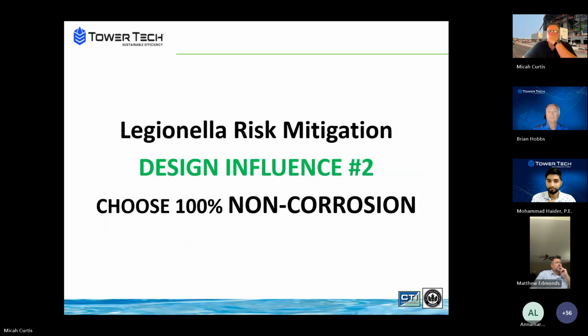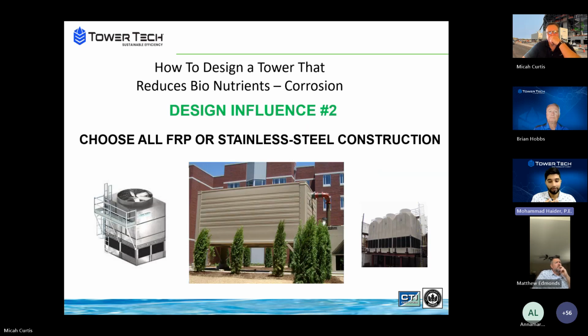Okay, pretty straightforward. Let's talk about the second influence. Yeah, so the second design influence that you can use to reduce the Legionella risk is to choose a non-corrosive tower design. As we discussed, corrosion itself is metal degradation due to chemical reaction, particularly of dissimilar metals, but even a standard metal. So galvanized towers, for example, the galvanized coating on a galvanized tower is actually zinc, whereas the internals are stainless, or carbon steel. So you have zinc and carbon steel. If you look at the galvanic charts, eventually you're going to get corrosion on that tower.